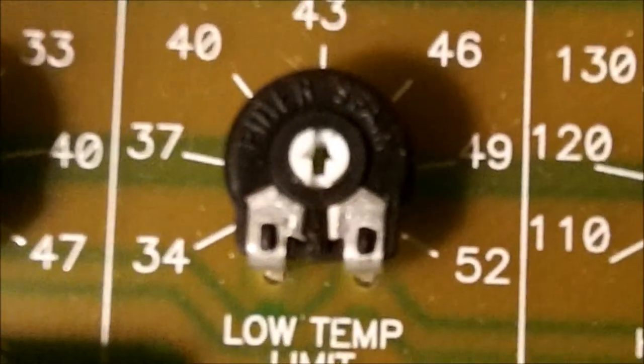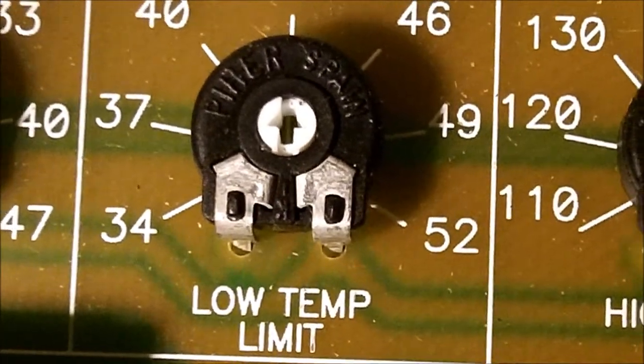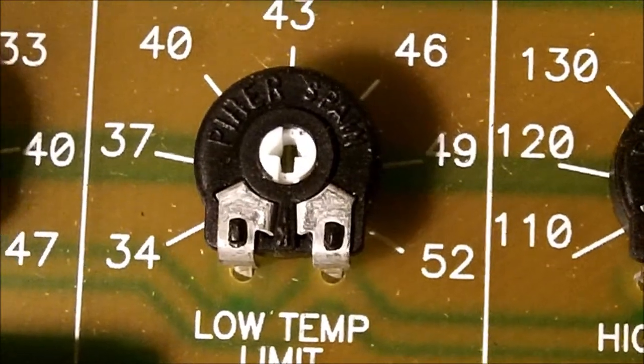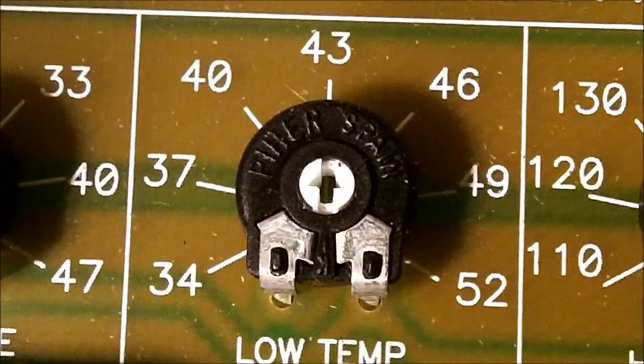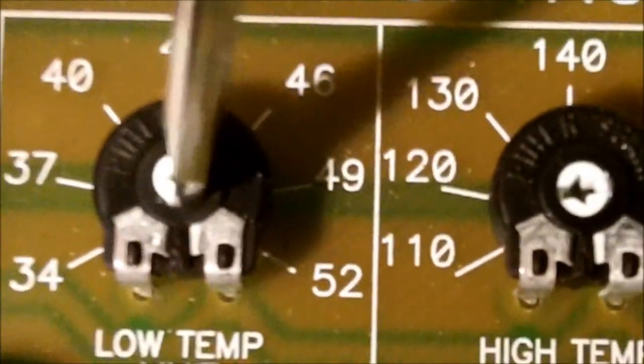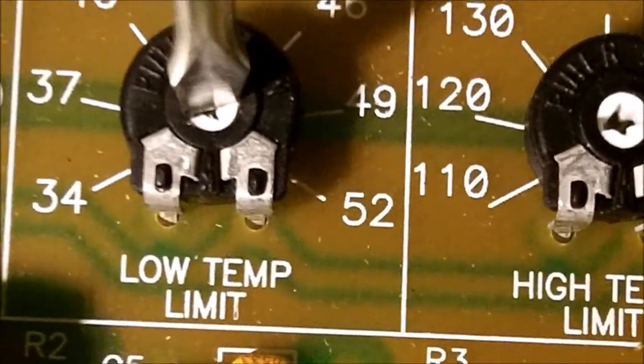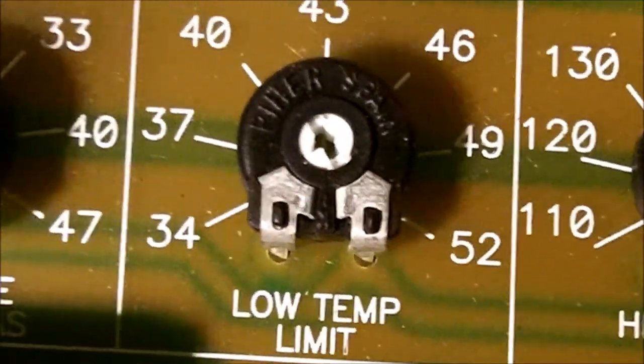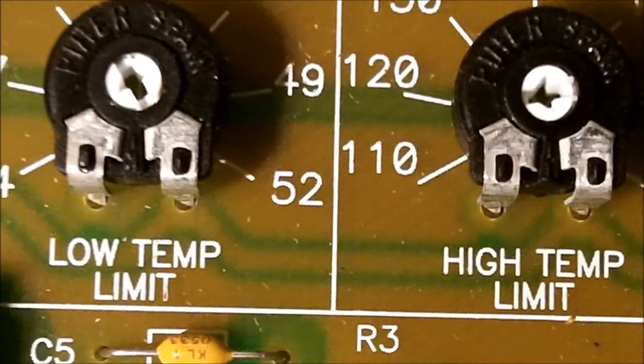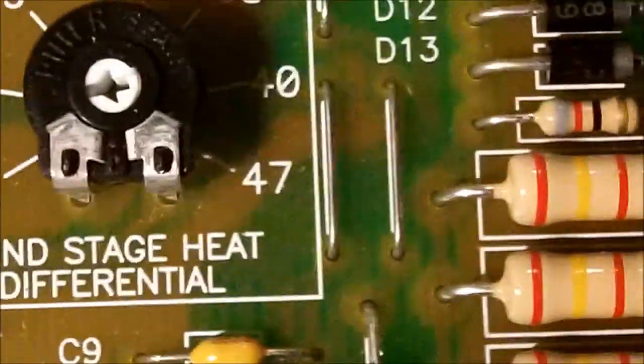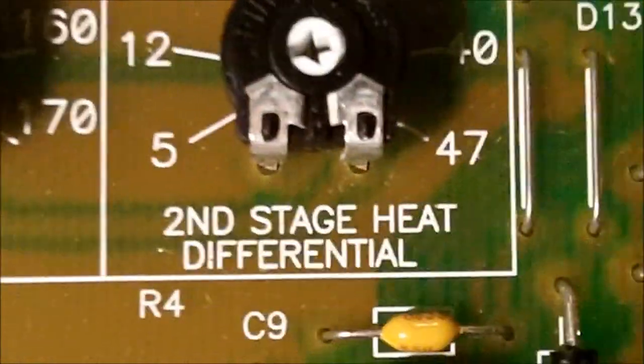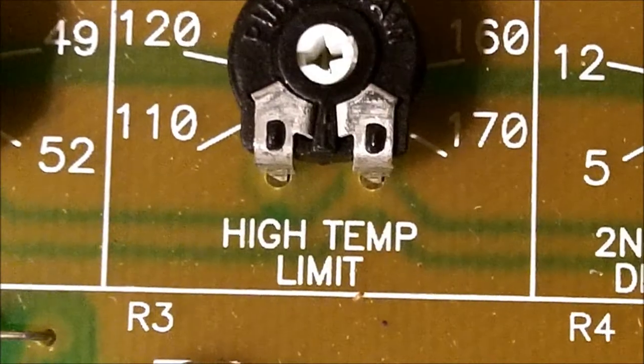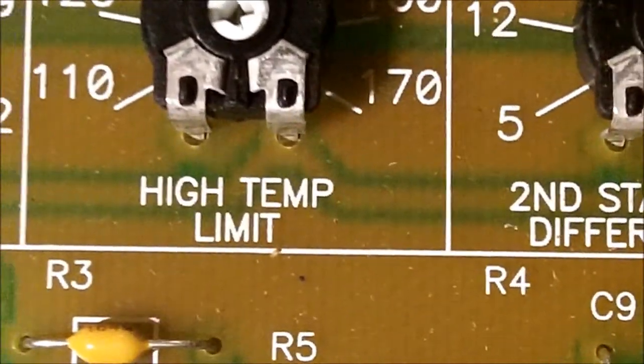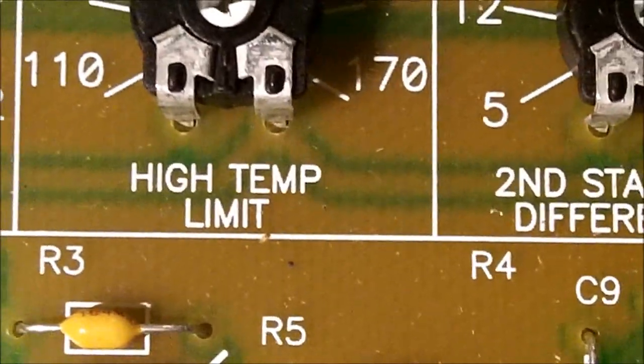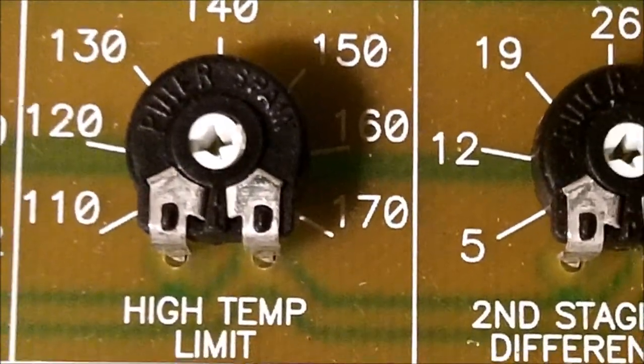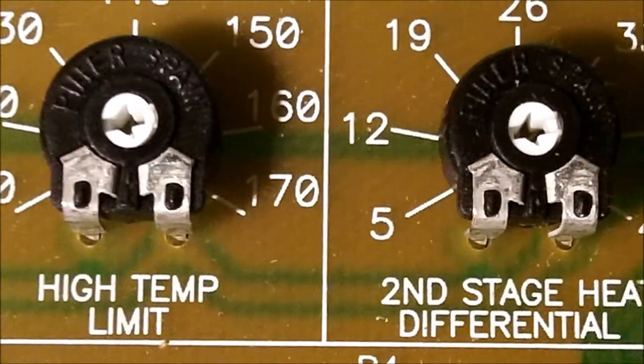The next dial is your low limit temperature, meaning for your air conditioning, and that's where your supply air sensor comes in use. You can set it all the way down to 34 degrees, 37, 40, 43, 46, 49, or 52. Okay, your next one is your high limit, and right now I've got it set for like 115 or something like that, but it's 110, 120, 130, 140, 150, 160, and 170 degrees.